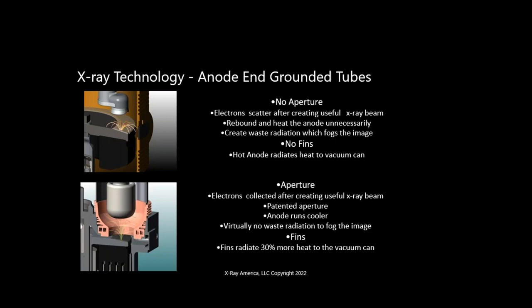There are also some diagnostic tubes that are coming to market. One of the key factors is that they run cooler. One of the reasons they run cooler is they put active cooling in these channels, so that you're actually pulling heat out of this anode right at the source. Heat generation.